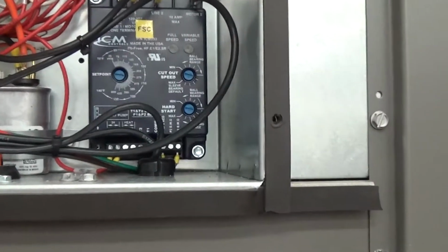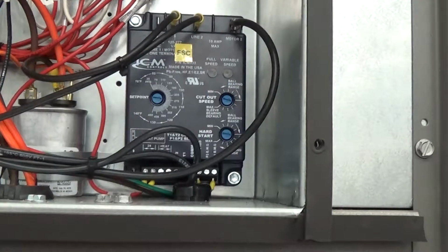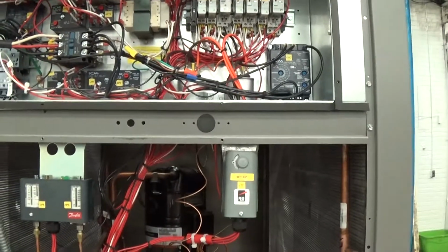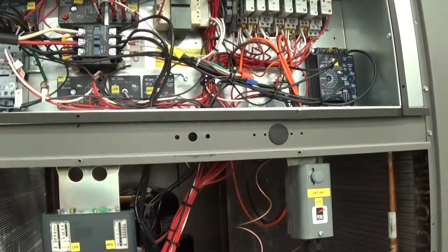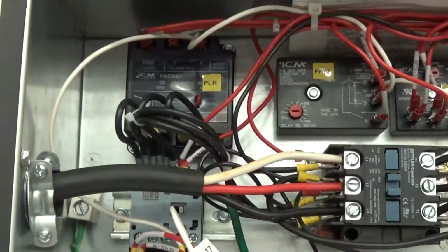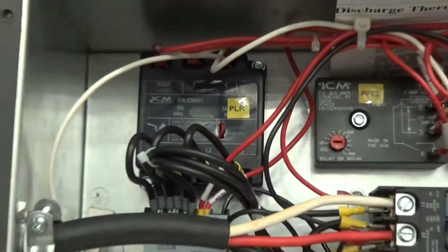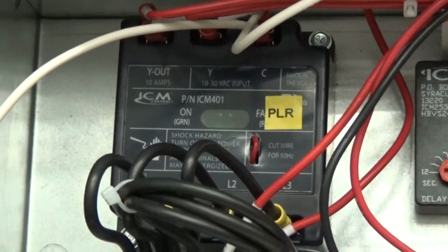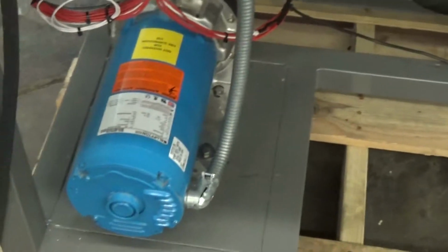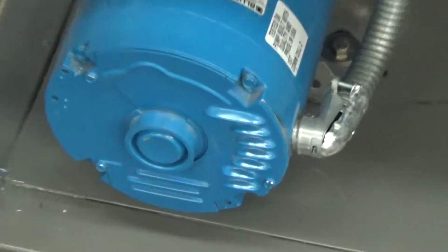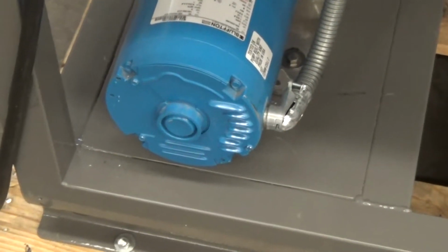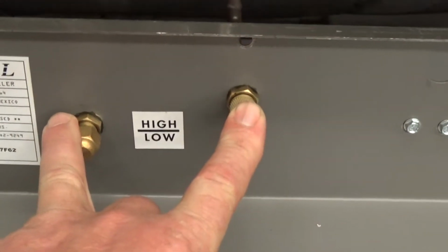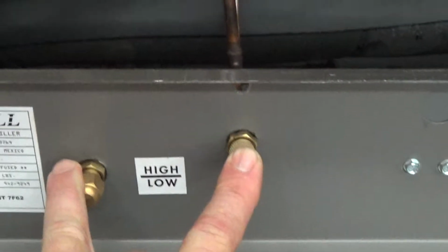Here we have our fan speed control. That's part of the low ambient circuit. Also up underneath here is a fan speed switch. So this achieves low ambient capability both by fan speed control and on-off fan switching. We also have our phase monitor here. If when you first start the unit up it's in the wrong phase, you'll probably see a red light come on this here. When you do first start up the unit, it is phase dependent, and you should check that with the pump rotation here, and that should be going clockwise from the rear. And here we have our high and low refrigeration ports if a technician ever needs to put on a set of gauges on the unit.